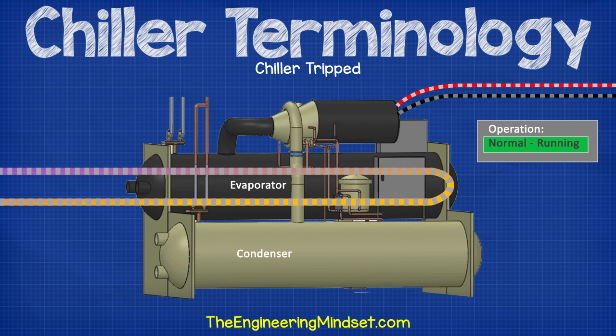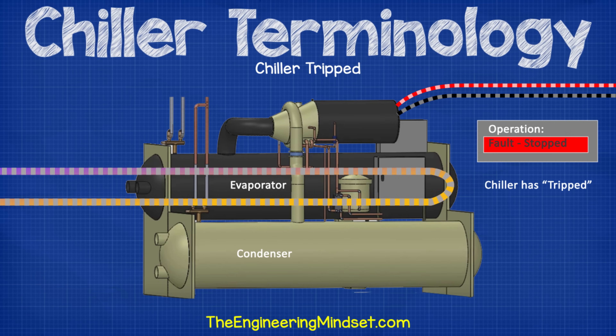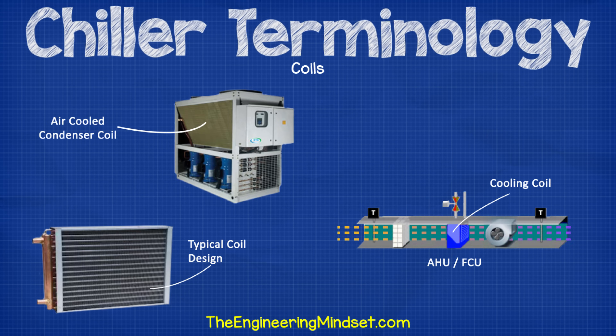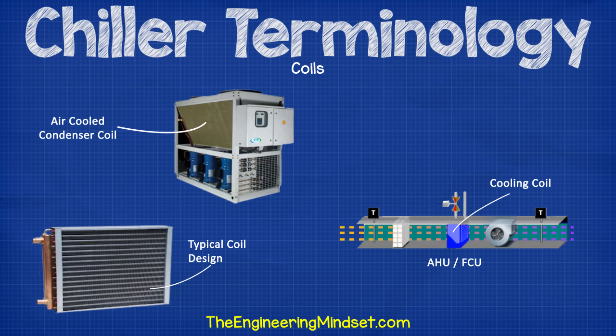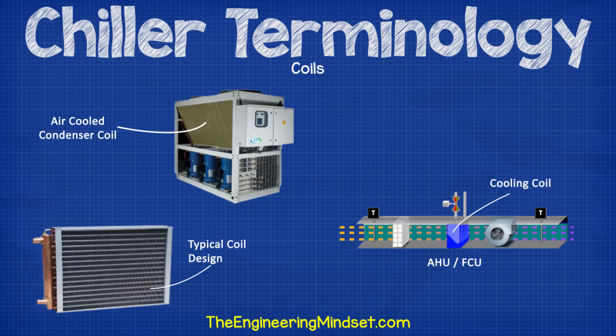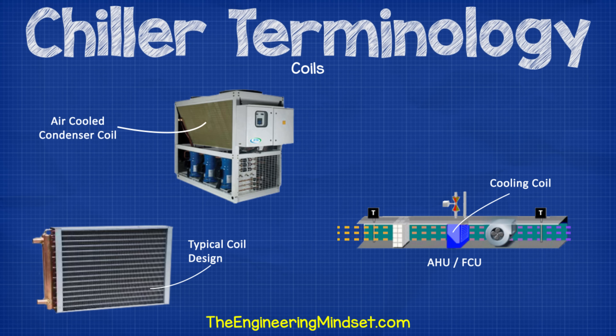Chiller tripped. This refers to the chiller turning off by itself through the internal controls due to a detected fault, or because it has reached the limits of a design set point — for example, a high or low pressure or temperature. The chiller therefore turns itself off to protect itself from damage. Coils. Coils refer to a heat exchanger. A cooling coil would mean a heat exchanger in an air handling unit or a fan coil unit which receives the chilled water and exchanges its cool into the air. A condenser coil would refer to the condenser of an air-cooled chiller which receives the hot, high-pressure refrigerant and uses the ambient air to condense this into a liquid.